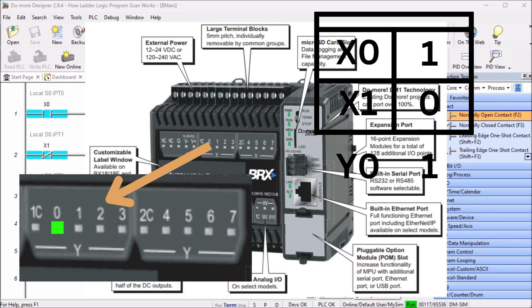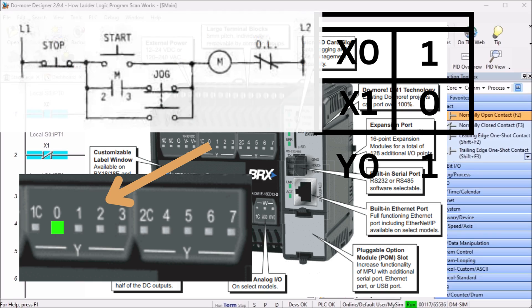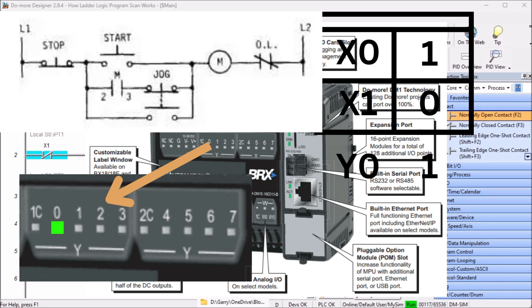A physically wired relay is a break before make device. When triggered, the relay will break open the first set of contacts before engaging or closing the new contacts. There is a time delay from breaking one circuit and engaging the next. Traditionally wired circuits, when replaced by a PLC, may have to change the logic slightly.